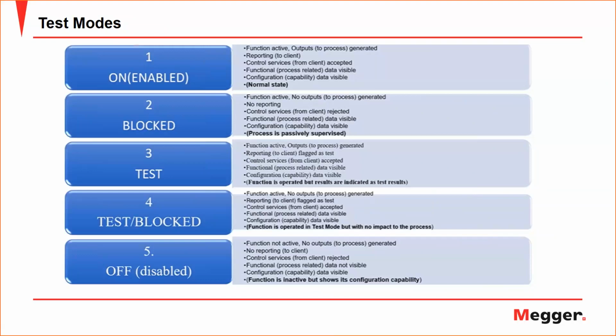Then we have a test/blocked mode. This was introduced mainly when people are using a combination of both digitalization messaging, like sampled values and GOOSE, and the physical contacts, for example, physical trip or operate contacts, or physical start or pickup contacts. The blocked condition will block these physical contacts, but will still publish the GOOSE messages since they are a hybrid system that uses both in combination. So this mode is very important.